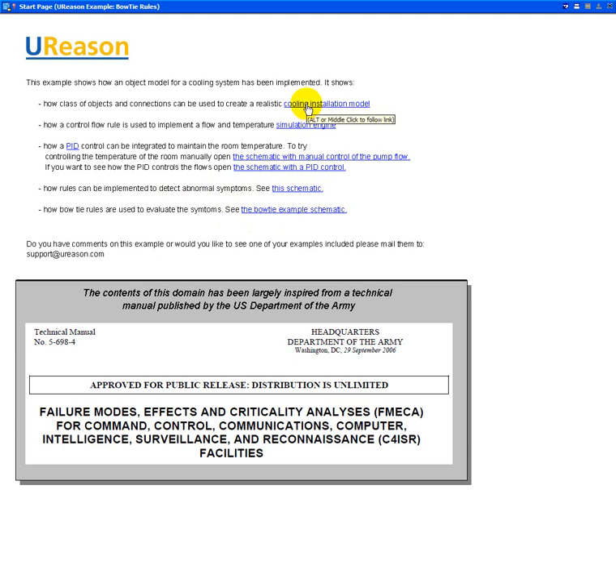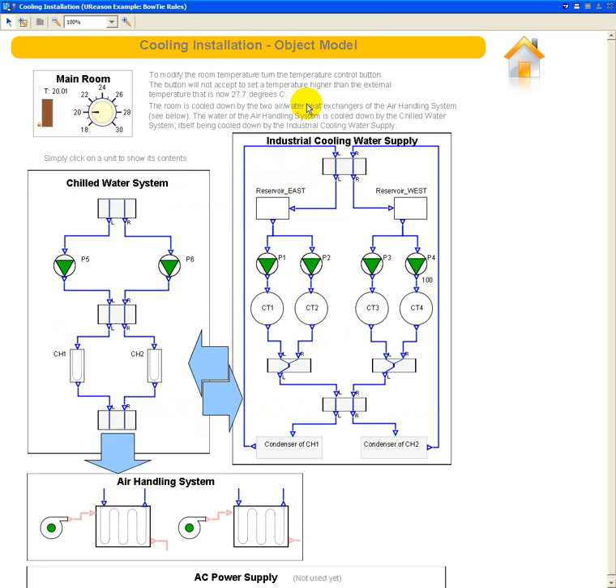So let's first drill into the cooling installation model. And as you can see, this model consists of several units. We have here at the bottom a power supply unit that's not being used in this demonstration. We then have an air handling system that is there to cool down the air coming from these fans and that will flow into the room. We have a chilled water system that is there to cool down the water of these heat exchangers. And then finally we have a last unit here, the industrial cooling water supply unit, that is there to cool down the water from the chilled water system.